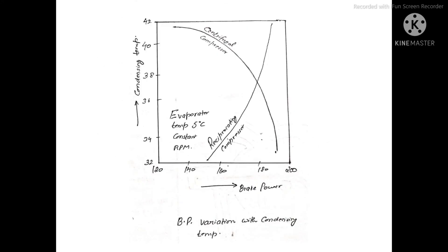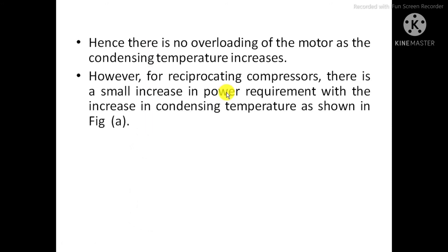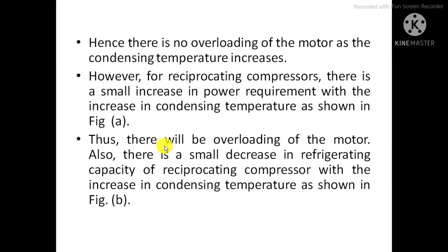For reciprocating compressors, there is a small increase in power requirement with increase in condensing temperature. This means there will be overloading of the motor in a reciprocating compressor, which is a disadvantage. Additionally, there is a small decrease in refrigeration capacity of the reciprocating compressor with increase in condensing temperature, as shown in figure B.